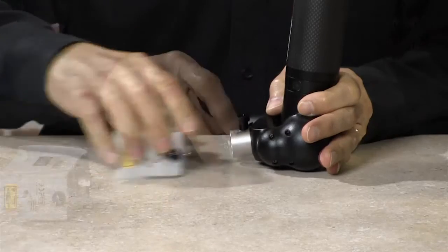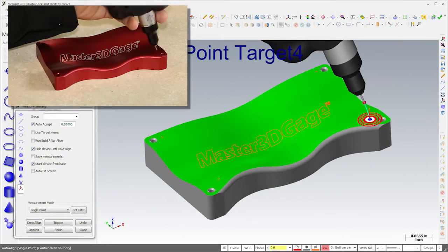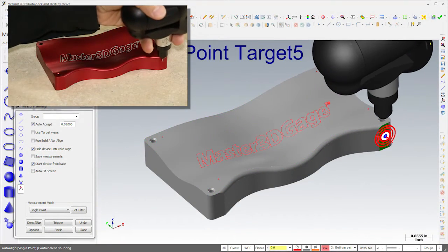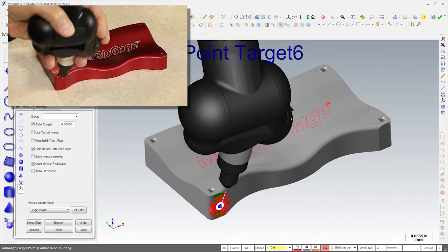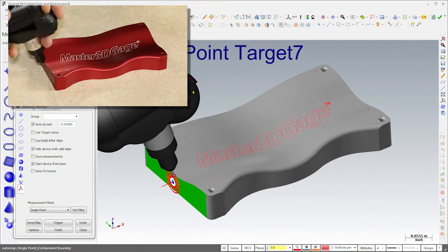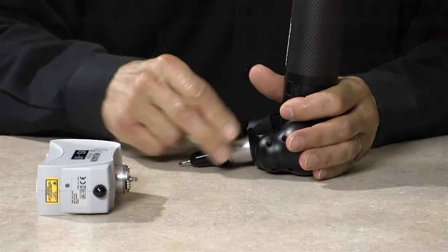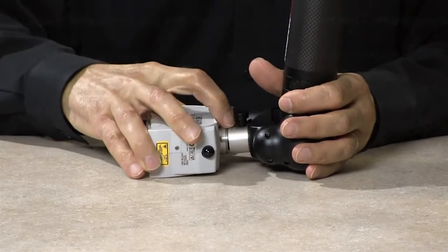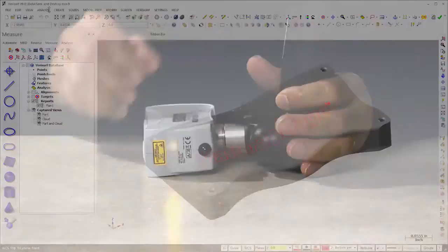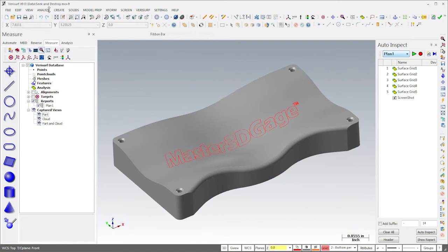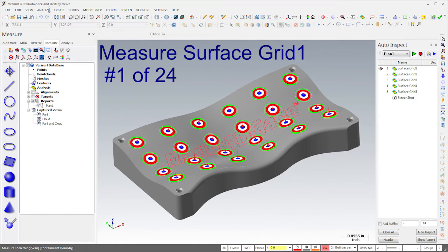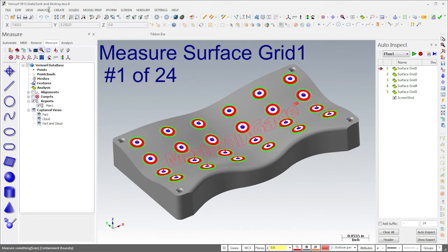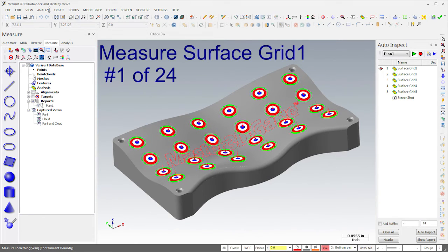I'll hot-swap the scanner for the probe and then align the Master 3D gauge using Auto-Align. When the alignment is complete, I'll hot-swap the probe for the scanner. The repeatable mount allows me to switch between probes without having to recalibrate. I'll then open Auto-Inspect and run the inspection plan. When I do, Verisurf highlights the targets in the first grid.